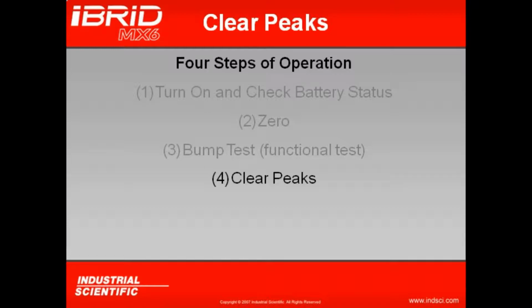The last step before we use the instrument is to clear our peak readings. What peak readings are is the instrument will store the highest toxic and combustible reading along with the lowest oxygen reading since the last time the peaks were cleared. Now peak readings are used so that if I'm in a confined space and the instrument starts going into alarm, the user's not going to want to sit there and start looking at the readings. Rather, they're going to want to exit. Now upon exiting, they can then check the peak readings to see what that concentration was that they were exposed to.